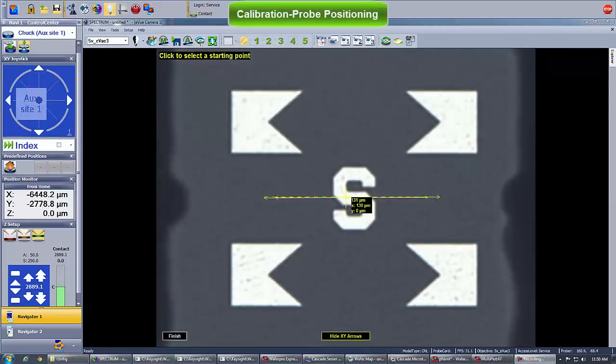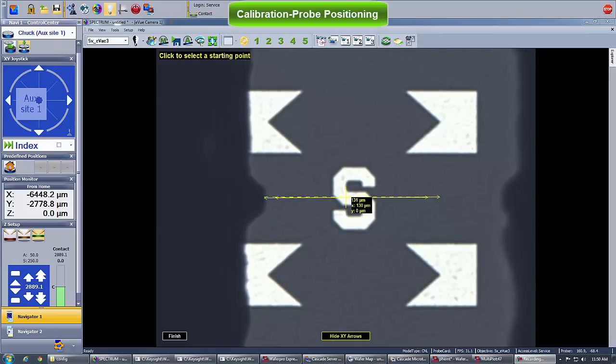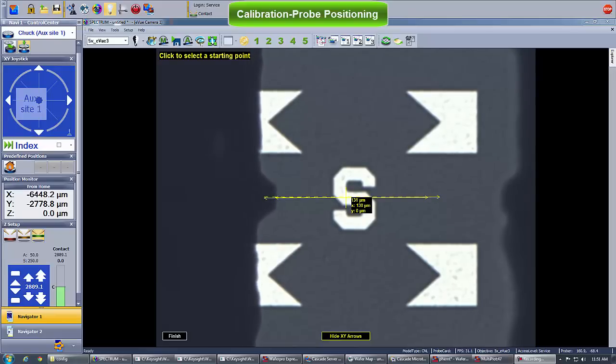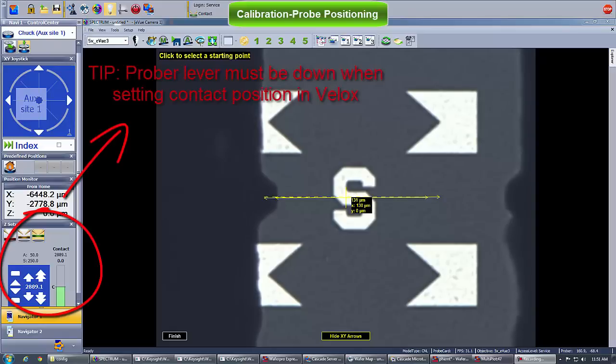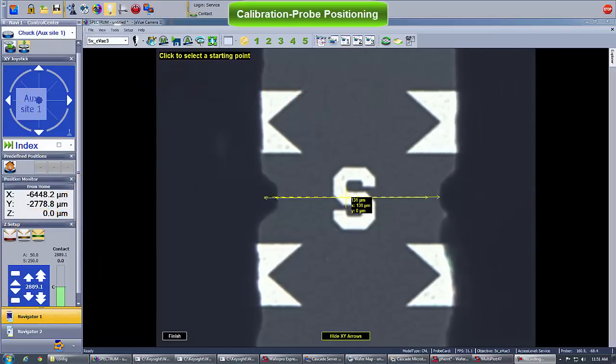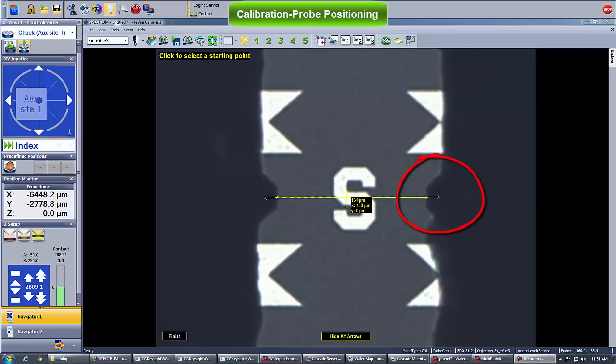Assuming that the ISS alignment to correct for any mounting angle has been run, let's now set the contact height and position the probes on one of the ISS alignment marks. To avoid damaging your probes, always make sure the prober main lever is down when setting the contact position in Velox. Probe positioning on the alignment marks does require some hands-on experience. Practice a few times until you reach a perfect probe landing and skating. This is really the key to a repeatable calibration.